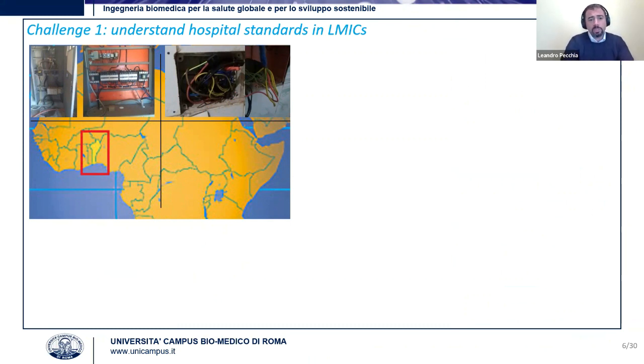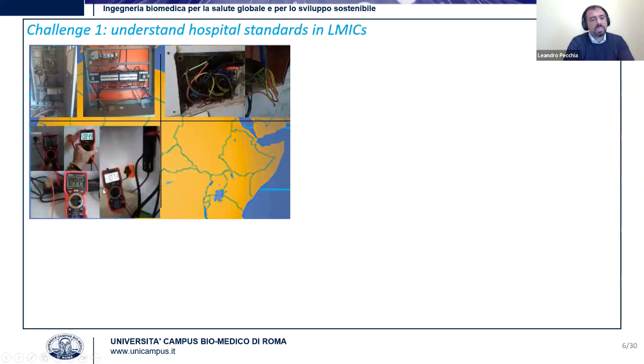This is work we did in 2014, where we started analyzing electrical plants in different hospitals - visual inspection of electrical plants - and then doing some measurements, very rudimentary. The first time we were not well equipped, but look at this number: we were measuring 100 volts on the ground of this medical device, and that's an issue because there should be no more than a few volts on the ground.